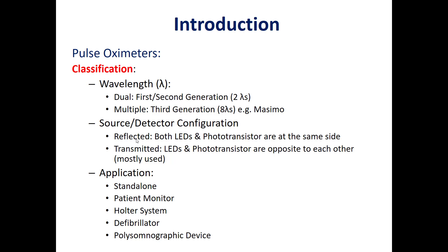In the transmitted type, we have two LEDs or many LEDs, depending on whether it is a pulse oximeter or pulse co-oximeter, and the source and detector are facing each other. This type is the most commonly used commercially.